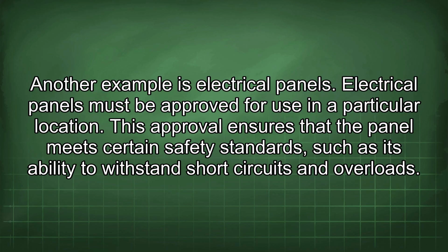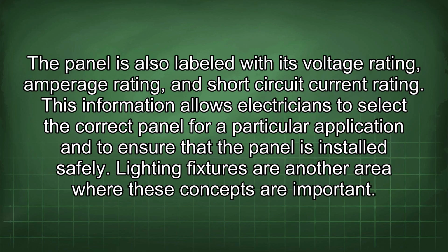Electrical panels must be approved for use in a particular location. This approval ensures that the panel meets certain safety standards, such as its ability to withstand short circuits and overloads. The panel is also labeled with its voltage rating, amperage rating, and short circuit current rating. This information allows electricians to select the correct panel for a particular application and to ensure that the panel is installed safely. Lighting fixtures are another area where these concepts are important.